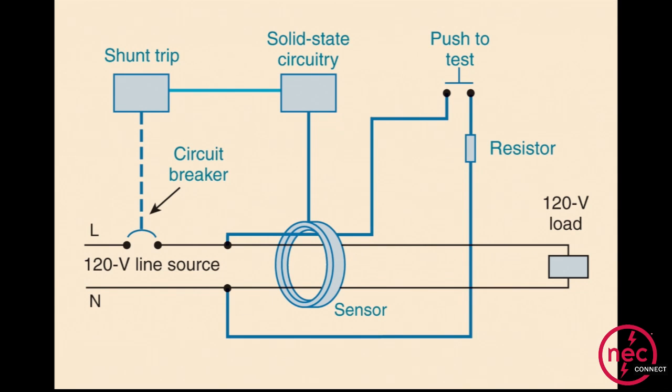One of the benefits of using a GFCI device in place of a two-prong receptacle is it gives you some protection. If you had a two-pronged device connected and there was a fault in the unit and you touched the enclosure, the ground fault circuit interrupter would give you protection that you absolutely have none of with a two-wire device. So it's required by the code to actually replace the two prongs with GFCIs, even if they're ungrounded circuits.